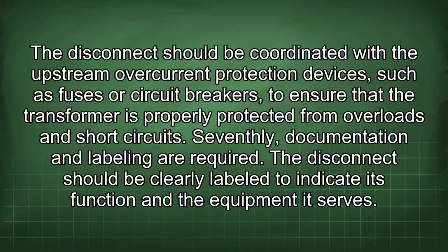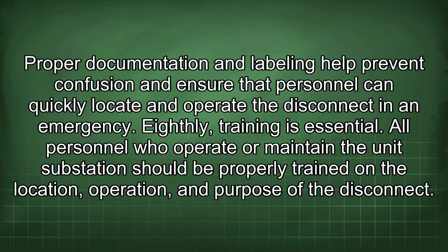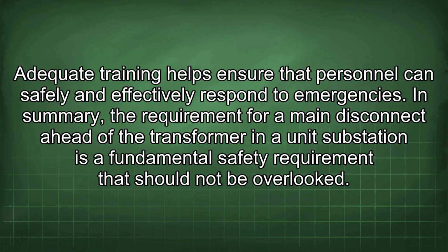Seventhly, documentation and labeling are required. The disconnect should be clearly labeled to indicate its function and the equipment it serves. Proper documentation and labeling help prevent confusion and ensure that personnel can quickly locate and operate the disconnect in an emergency. Eighthly, training is essential. All personnel who operate or maintain the unit substation should be properly trained on the location, operation, and purpose of the disconnect. Adequate training helps ensure that personnel can safely and effectively respond to emergencies.